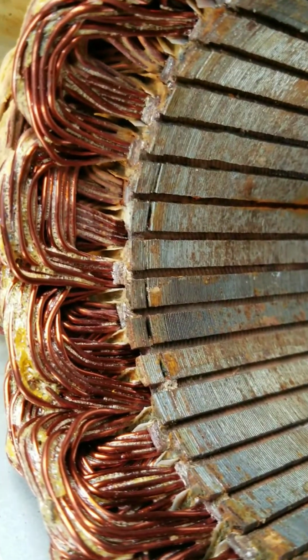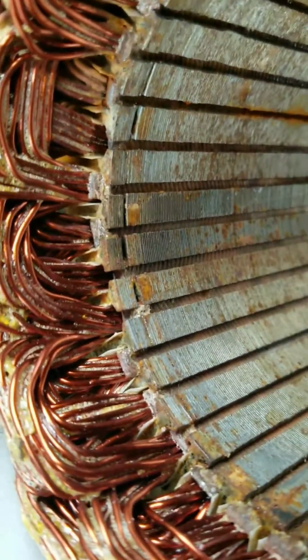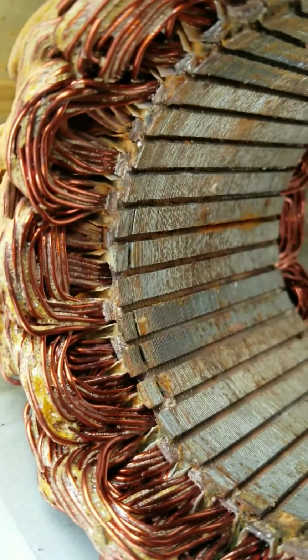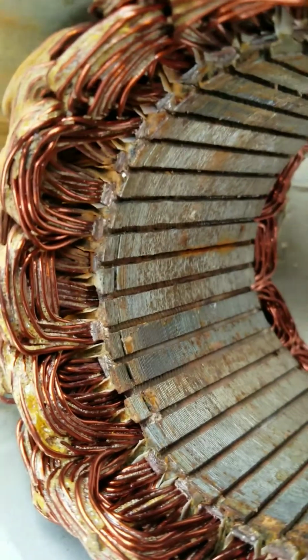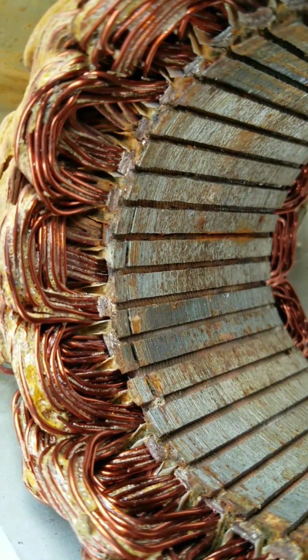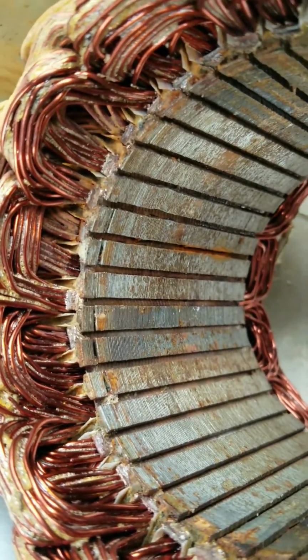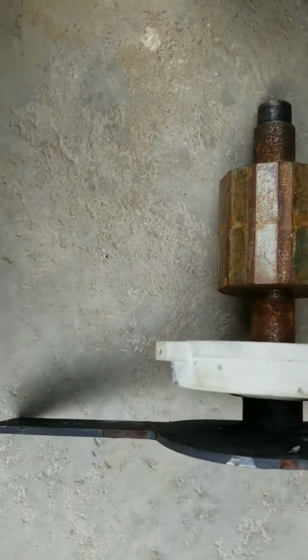There you can see the laminations have separated there. So I can't say if that was a manufacturing defect or if that happened after the fact, but the rotor wasn't scraping or anything like that in there. The bearings were still good. And you can see they're not exactly straight, but the next thing I'll get to, and this is my main beef, is the rotor.